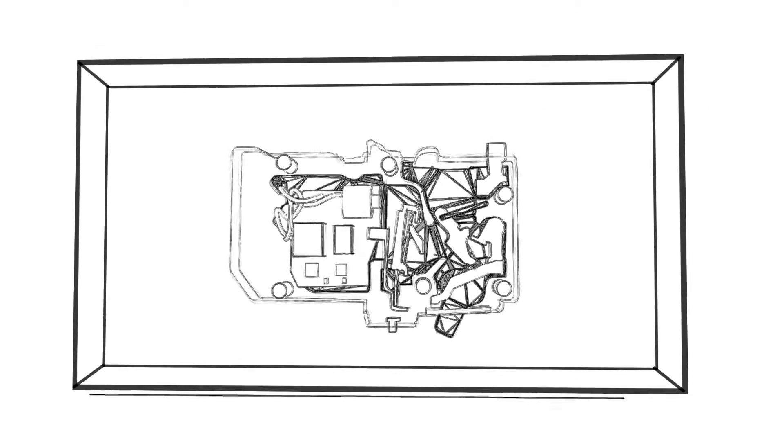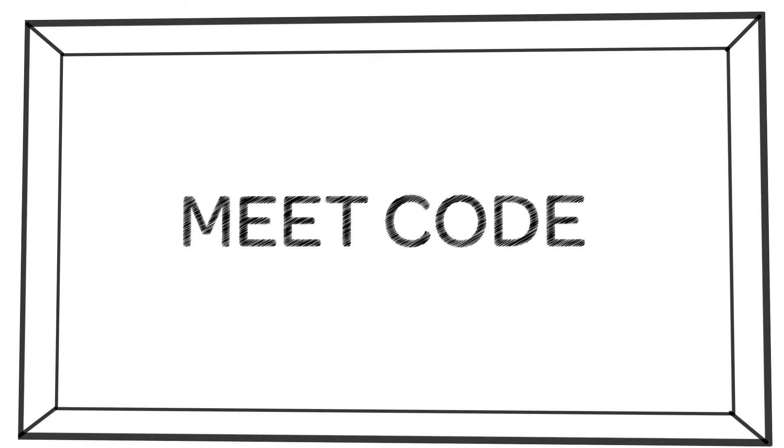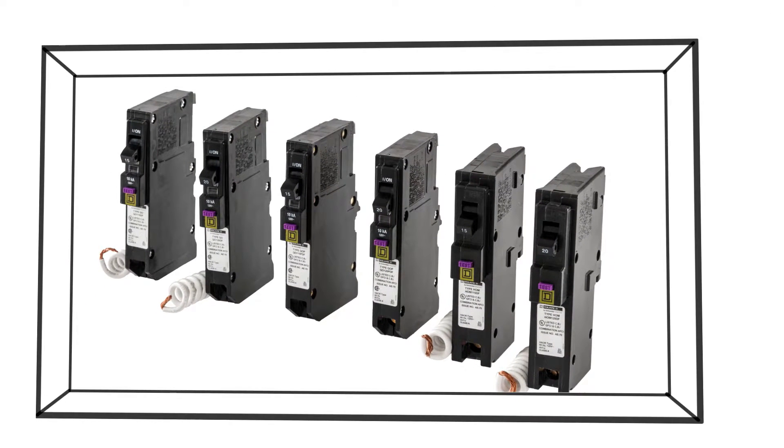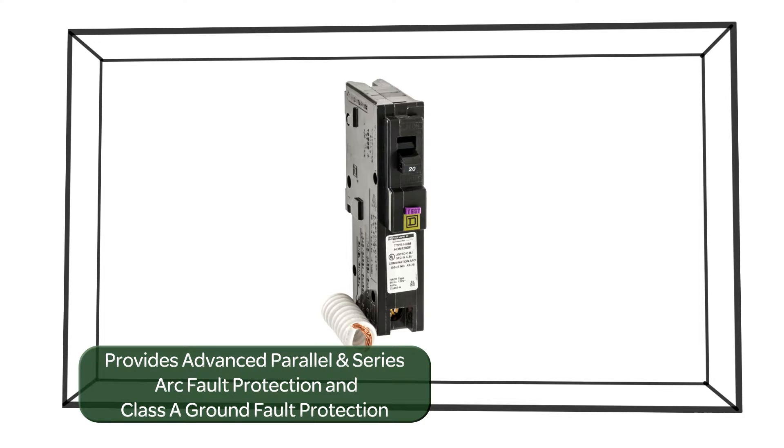This is another money saver for you, simplifying both the wiring and cost of providing code required protection for these circuits. The breaker is integrated with Square D's industry-leading arc fault detection firmware that provides advanced parallel and series arc fault protection, along with time-tested class A ground fault protection.